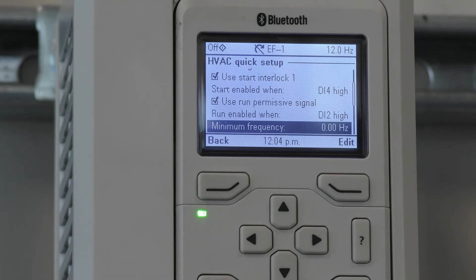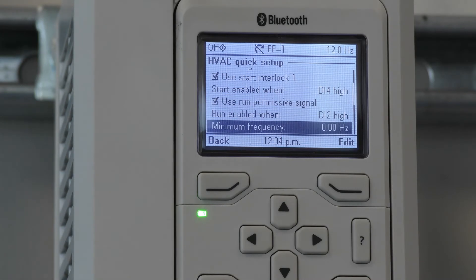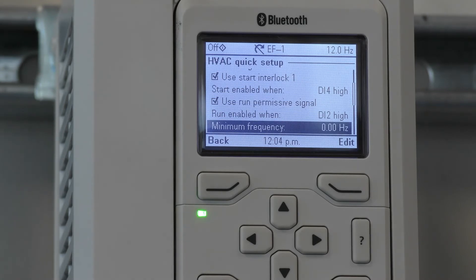The next parameter is minimum frequency. This is typically edited to not go any lower than 6 hertz, which allows the motor to cool itself at that speed. Some motor or pump manufacturers prefer an even higher minimum frequency to help protect the motor or pump.